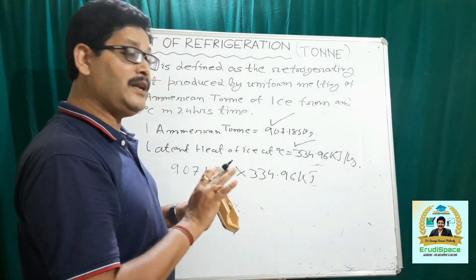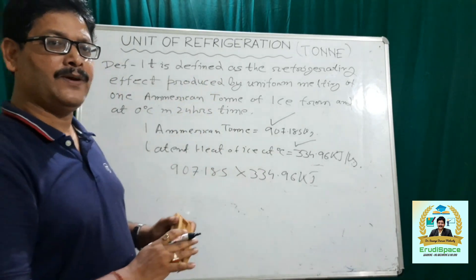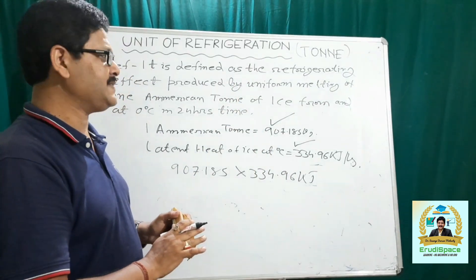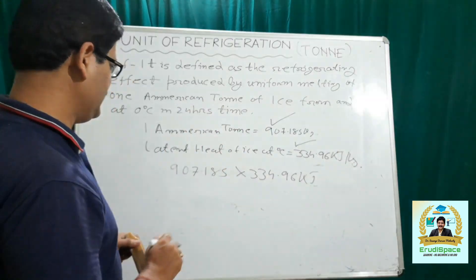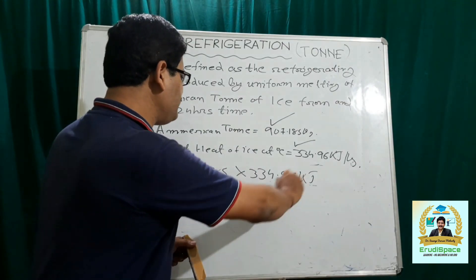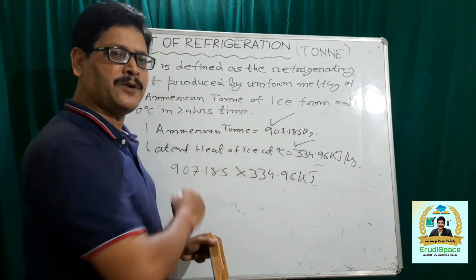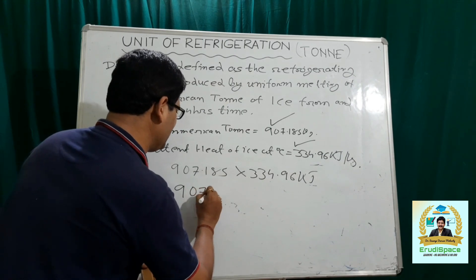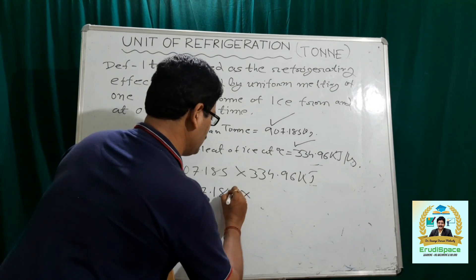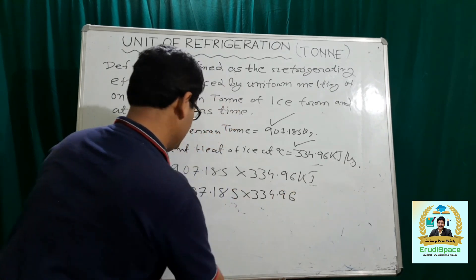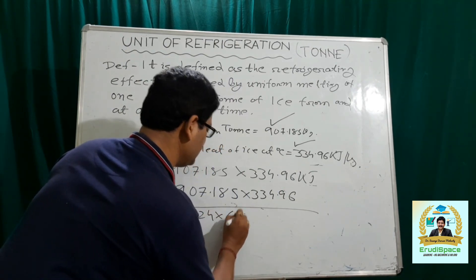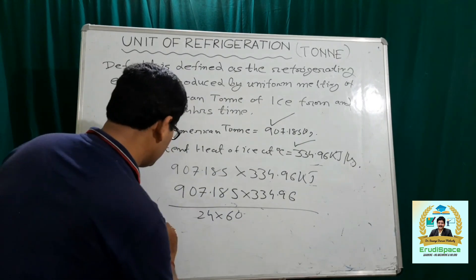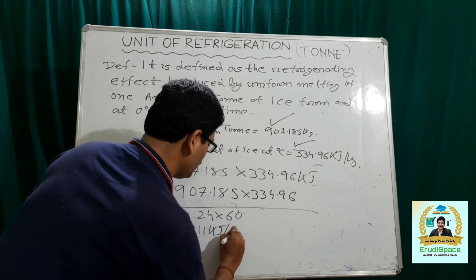Here we are only considering the latent heat removal, because from the definition itself, only the refrigerating effect equivalent to melting of one American tonne of ice from and at 0 degrees Celsius is being considered. This heat removal is over 24 hours time. In one minute, the amount of heat removed is 907.185 multiplied by 334.96, divided by 24 multiplied by 60 — because in one day you have 24 hours and in one hour you have 60 minutes. That is approximately equal to 211 kJ per minute.